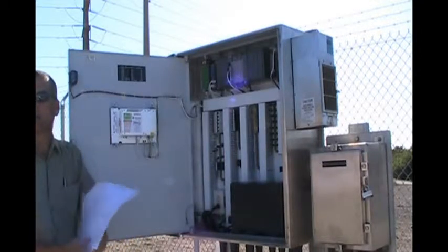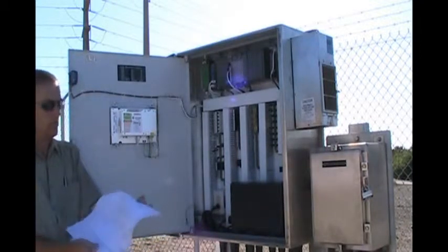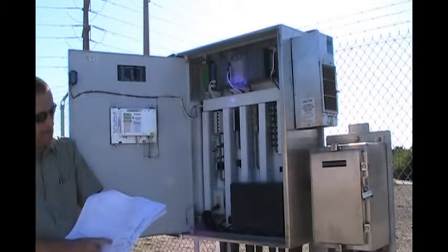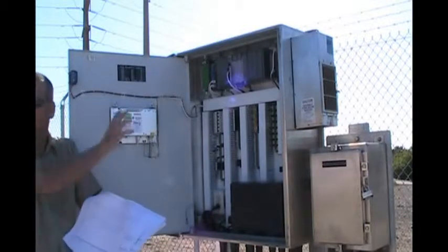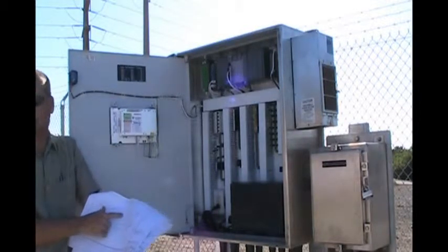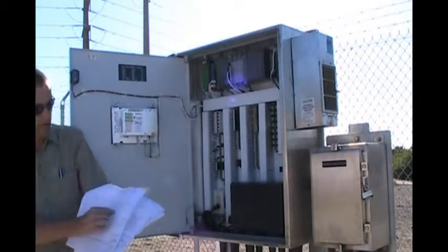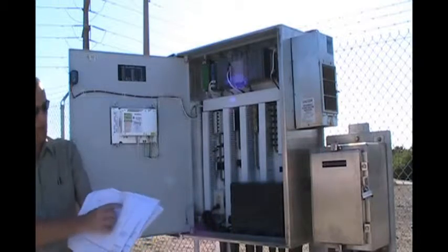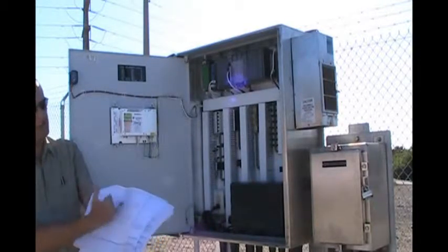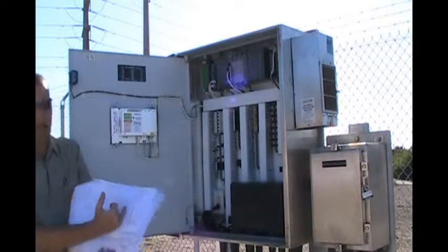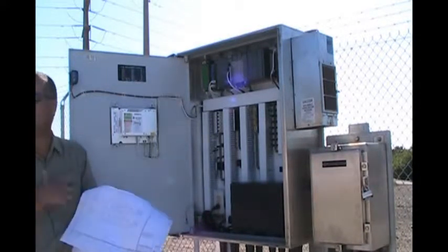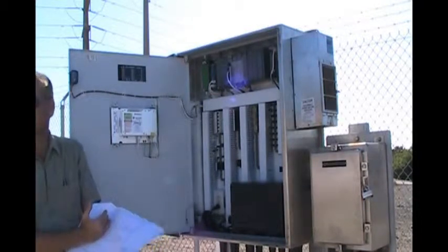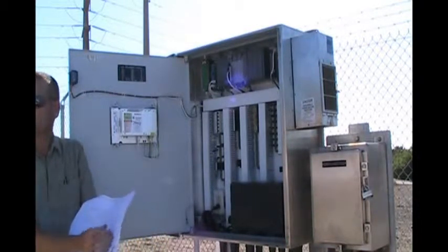It's a loop drawing of the instruments at the site. The way this is set up is on the right-hand side is the actual RTU. And then you have a dividing line, and anything that goes from this RTU into Weymouth's cabinets, which are over there, they're going to land it somewhere, and when we get it, we'll give you the real numbers. And then from their cabinet, it goes to field. So the left column is field, center column is MWD's cabinet, right column is IUA's cabinet. And that's how this entire project, these drawings are laid out. If there's no MWD involved, it would be left side is field, right side is RTU, IUA, RTU.